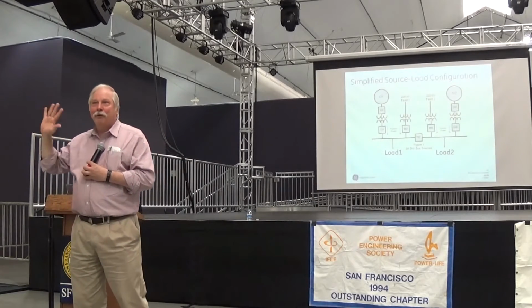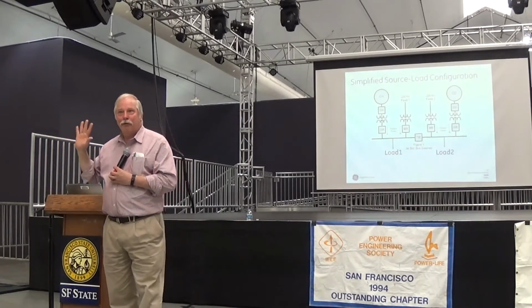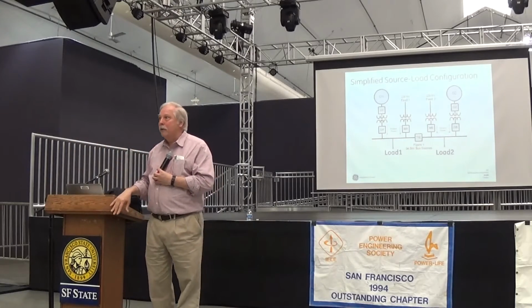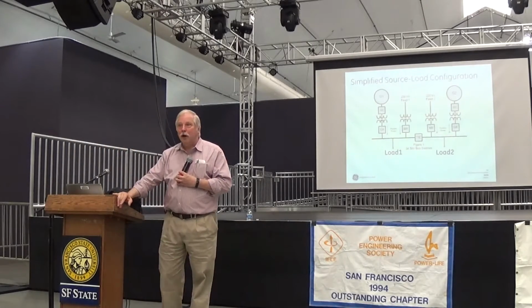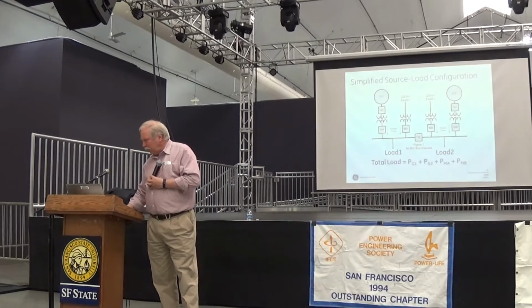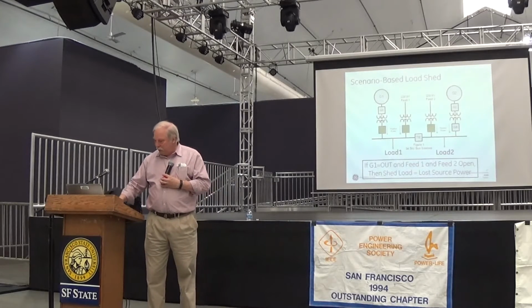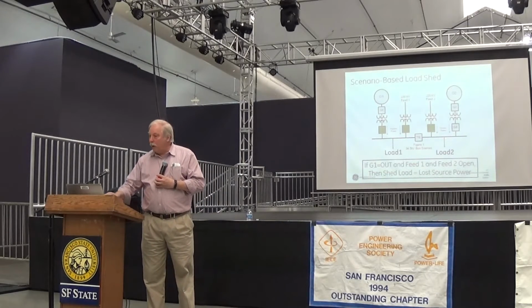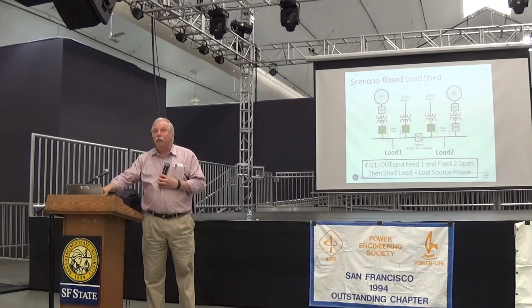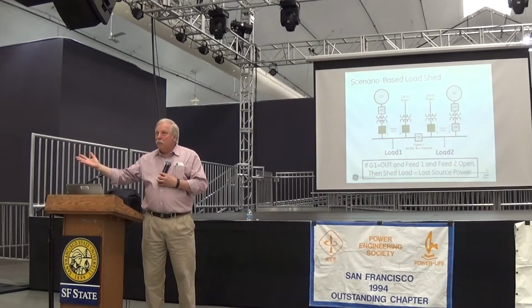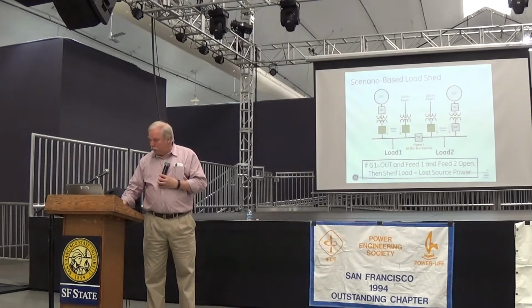The probabilities are small, but it's happened, and it's cost this plant literally multiple millions of dollars. So, bottom line is, it's possible today to detect these outages, and when you detect these 3 breakers being out, as an example, this is an immediate trigger for load shed.